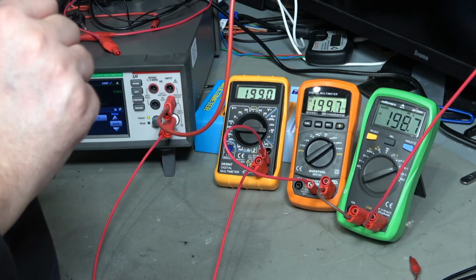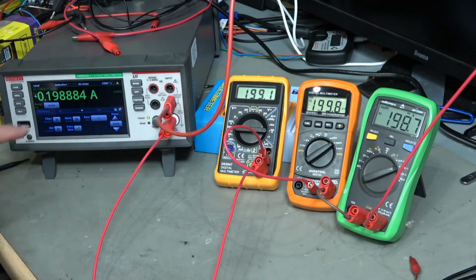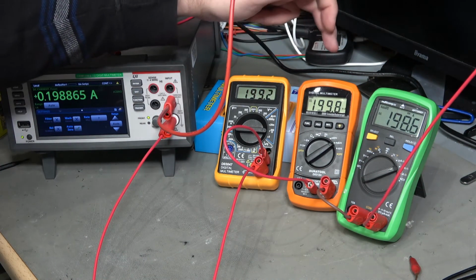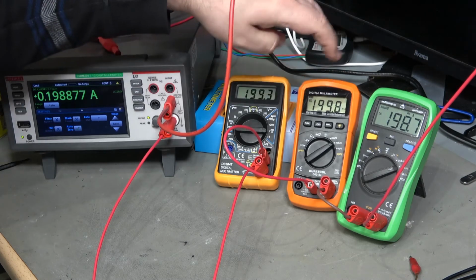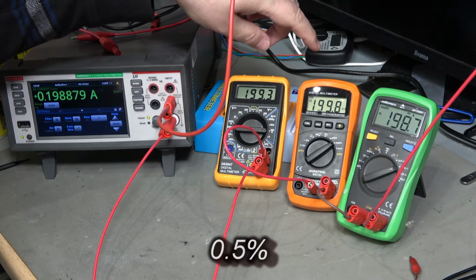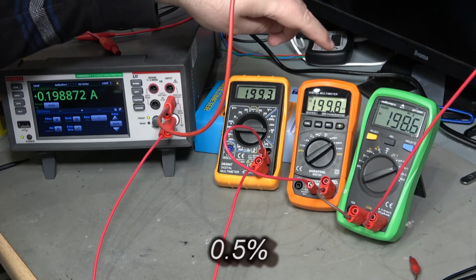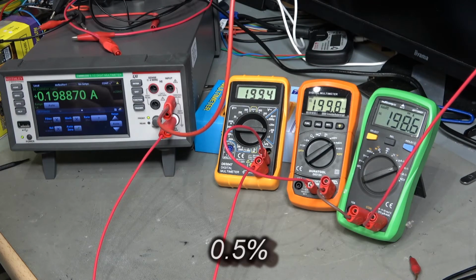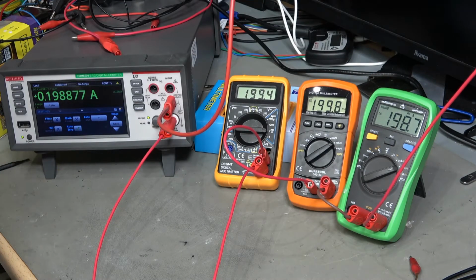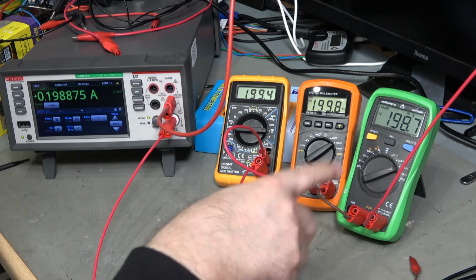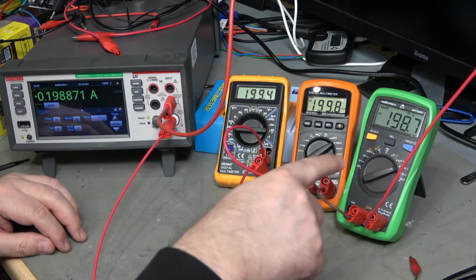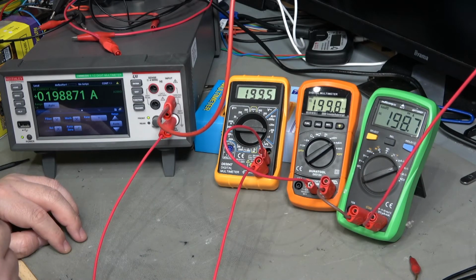Okay, so I've asked for 199 milliamps and I'm getting 198.87, 199.2, pretty good, 199.78. So this one actually is overreading by about a milliamp, which is nothing much. It's only 0.5% error. 198.7, and it should be 198.8. So yeah, that's a tiny error, 100 microamps error. That's all. So nothing much at all error-wise on that, 0.1% or something.